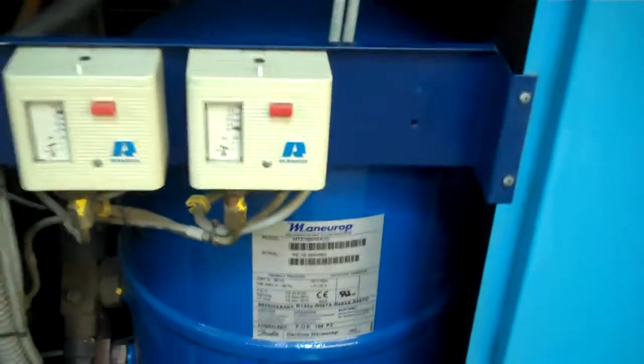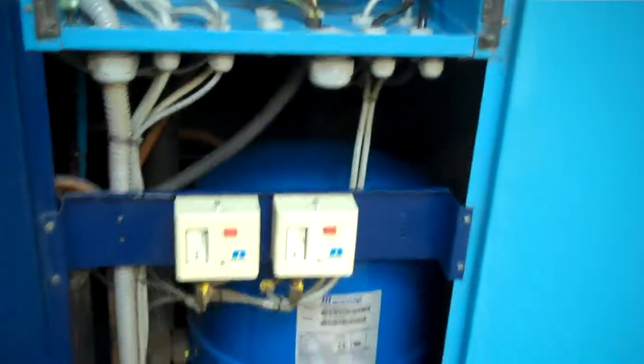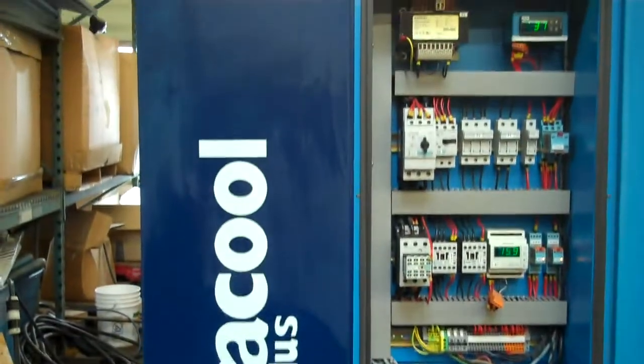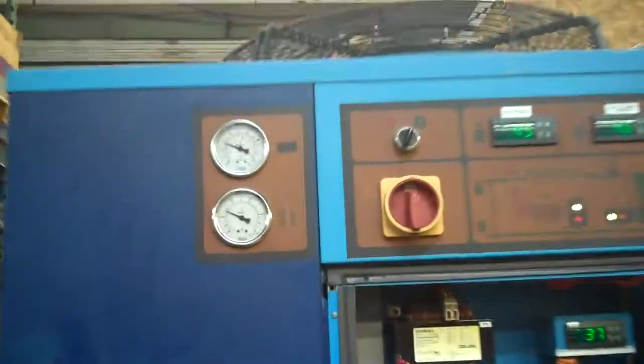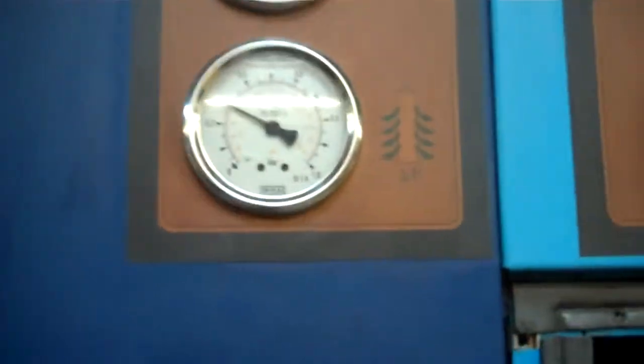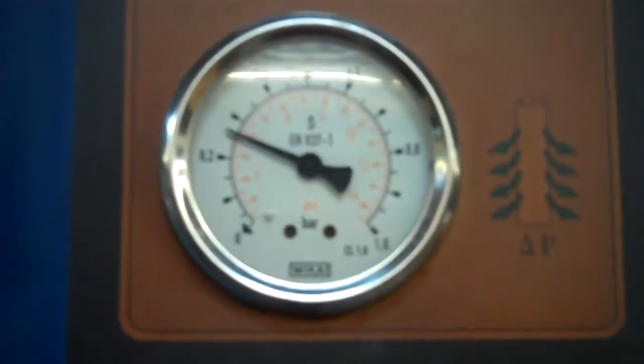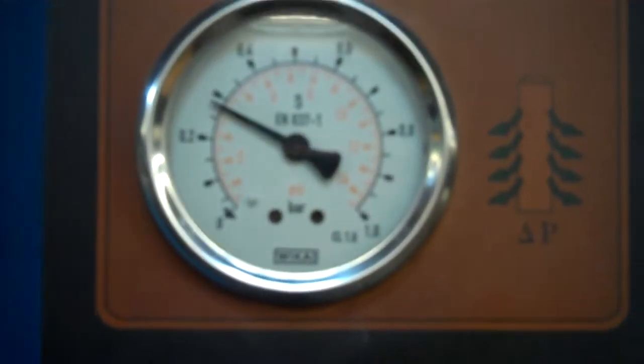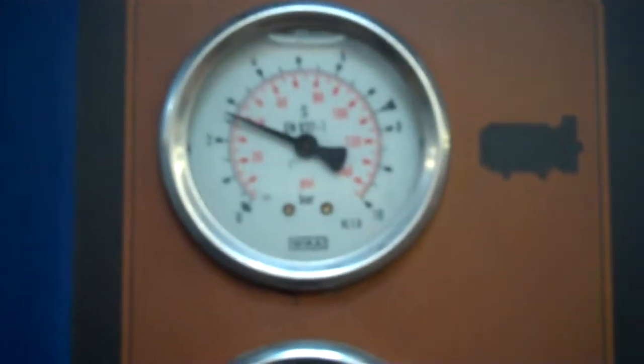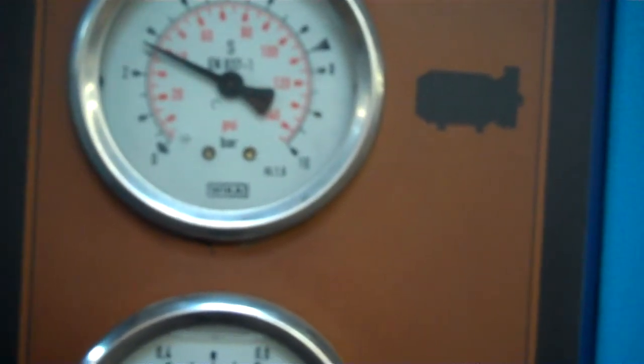It's worth mentioning these Maneurop compressors always seem to run quieter and quite frankly longer than any of the other Danfoss and other compressors we've seen on all the many chillers that come through here. We have two gauges. One here is showing our water pressure at the heat exchanger, and our main pump pressure also here.